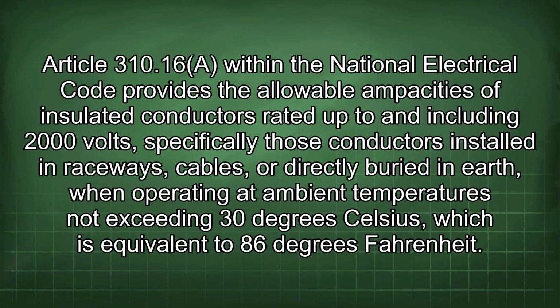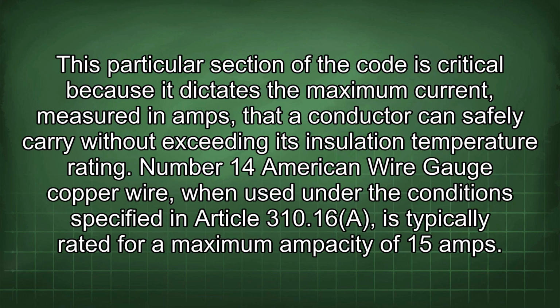Article 310.16 within the National Electrical Code provides the allowable ampacities of insulated conductors rated up to and including 2000 volts, specifically those conductors installed in raceways, cables, or directly buried in earth, when operating at ambient temperatures not exceeding 30 degrees Celsius, which is equivalent to 86 degrees Fahrenheit. This particular section of the code is critical because it dictates the maximum current, measured in amps, that a conductor can safely carry without exceeding its insulation temperature rating. Number 14 American wire gauge copper wire, when used under the conditions specified in Article 310.16, is typically rated for a maximum ampacity of 15 amps.